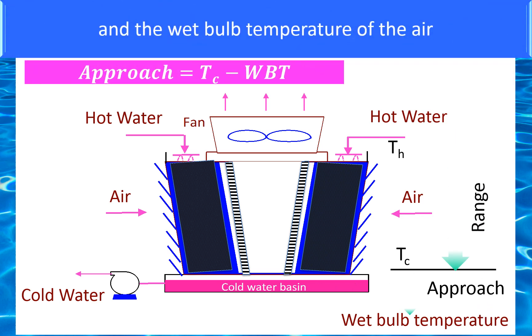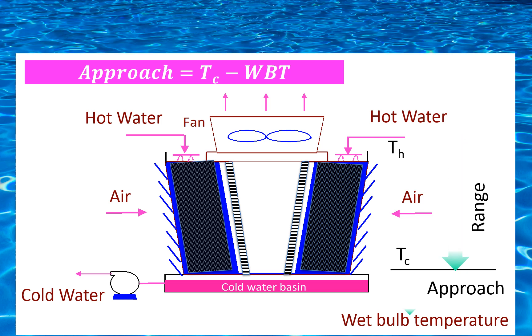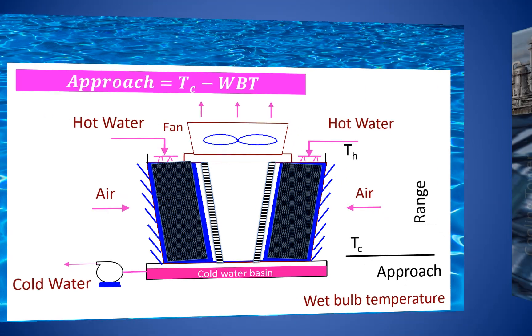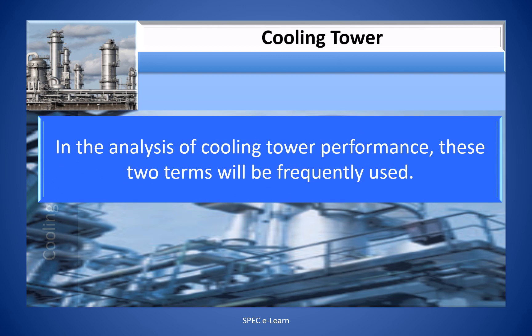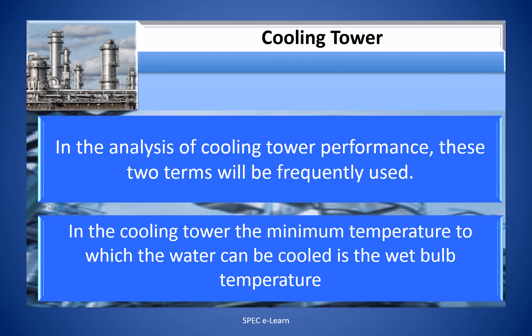Approach is the difference between the temperature of cold water leaving the cooling tower and the wet bulb temperature of the air: Approach = TC − WBT. In the analysis of cooling tower performance, these two terms will be frequently used. The minimum temperature to which water can be cooled in a cooling tower is the wet bulb temperature.